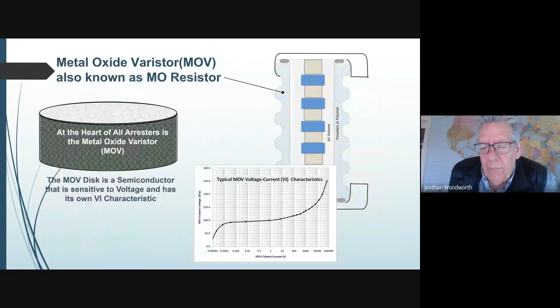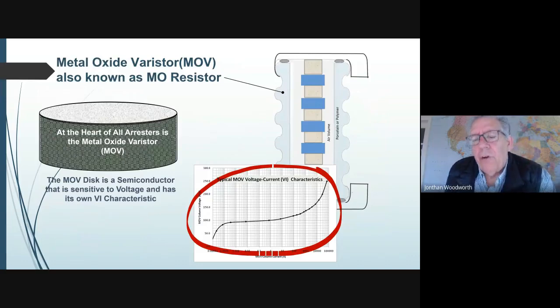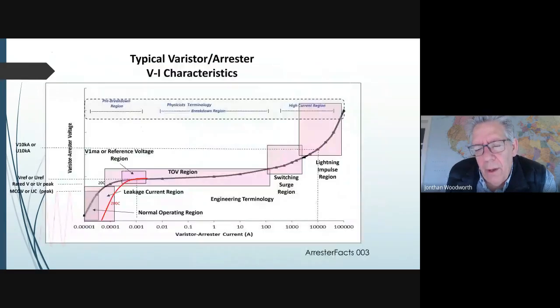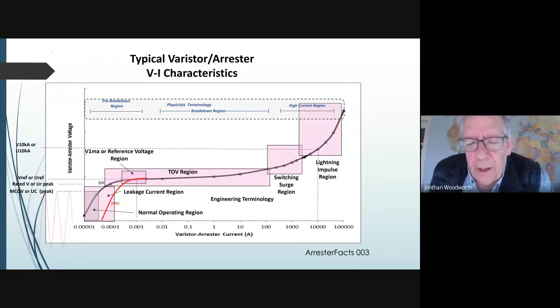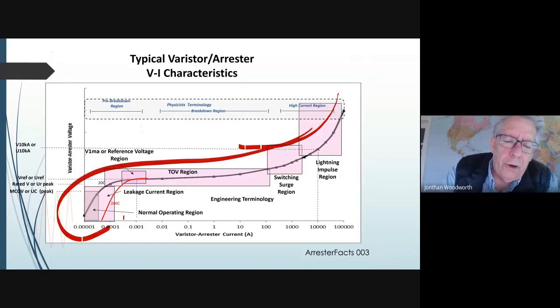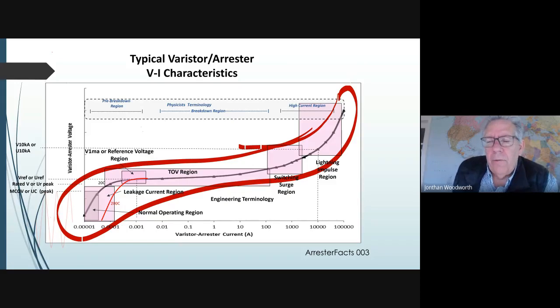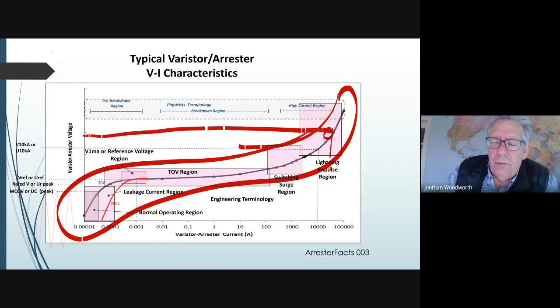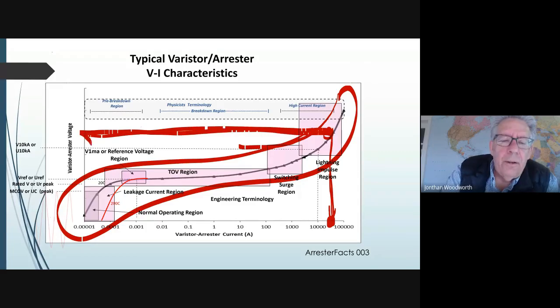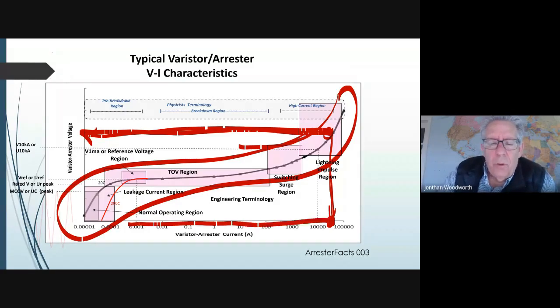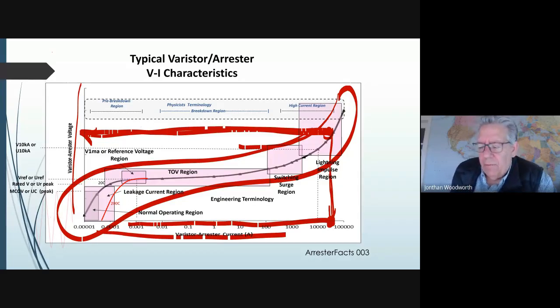This is the characteristic curve of an arrestor. And it's really important if you're an arrestor designer. It's not so important to the user. And all arrestors have it. And if you're ever going to do a lightning study, though, using ATP or EMTP or any kind of transient software, you would have to know this characteristic curve. I'm not going to go into it today, but it is an important curve. It shows you at what voltage and current you'll have. So if the lightning strikes and it has 50,000 amps, you'll know that the voltage across the arrestor is going to be at some level. So it tells you very precisely for different current levels what the voltage levels will be. So it's like any characteristic curve of any semiconductor.